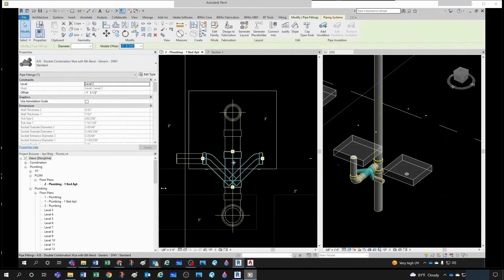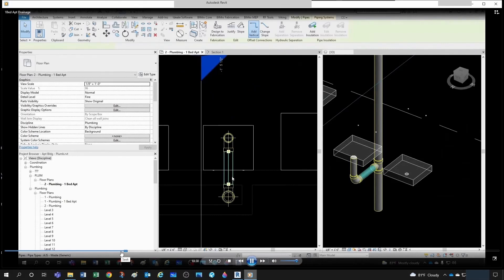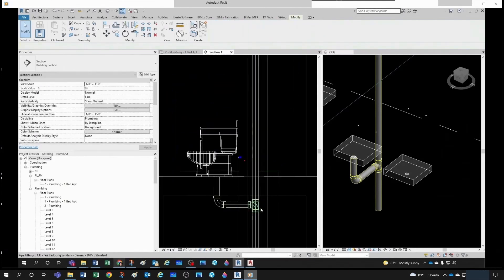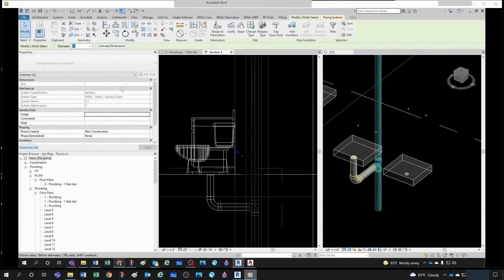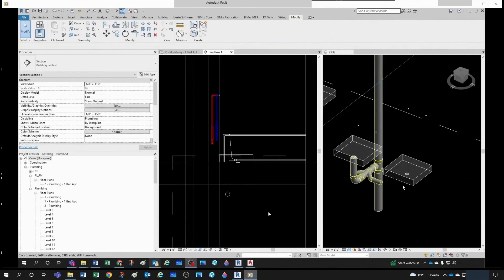Now we want to connect to our tub — we'll take a two-inch line. I'm changing this sanitary tee into a double sanitary tee and then, using my routing preferences, turning that into a double combination Y-⅛ bend. This piece of pipe is supposed to be sloping down, but when it gets to the combination Y-⅛ bend, this is a double fitting in a horizontal plane — so both arms of the fitting are horizontal, not sloped. Strictly speaking, you're not compliant because you're not sloping your pipe all the way down to the connection.